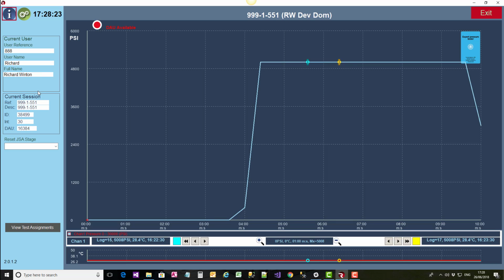Now, there's a change user button there, but it's currently disabled because I've just vented down, and the system hasn't been able to collect enough log points after the vent down to figure out if the system is stable or not. So essentially we need to collect 5 log points. That's what we've got it set to.